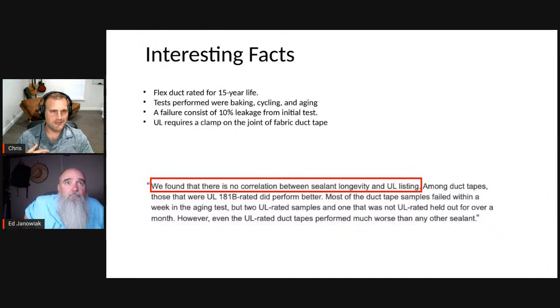They basically said flex ducts are rated for about a 15-year life. I never really heard that before I read the article - I didn't know there was a time limit to it. The tests performed were baking, cycling, and aging. A failure consisted of 10% leakage from the initial test. At that 10% leakage, that's when they say this tape has failed. So just letting everybody know, that's the failure rate for this test.